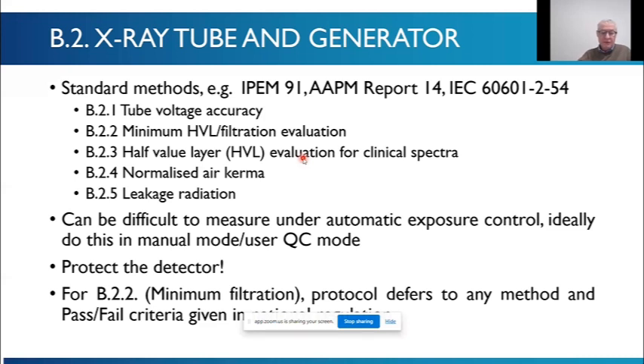So the half value layer is changing all the time, and you want to evaluate those at the commissioning test, to see that the HVL is changing appropriately. Then there's a normalized air kerma, or the yield, or you might call it the X-ray tube output, measured at about 80 kV, and then leakage radiation. This may or may not be done by you, as in diagnostic X-ray physicist or medical physicist. It may be done by some other department, like it's done here in the hospital by other colleagues. But that is specified in the protocol.